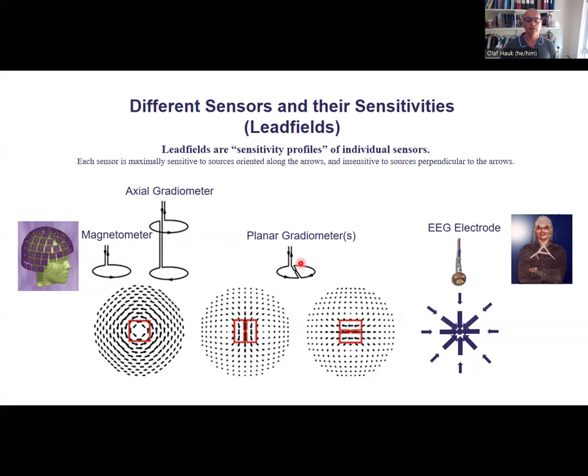And then there are also planar gradiometers. In this case, you have a similar arrangement. One coil here, one coil there. They are subtracted from each other, but they are next to each other in the same plane. It has the same effect. Homogeneous magnetic fields will cancel each other out. That means distant sources will be suppressed. Nearby sources will produce the biggest difference in these two coils. But this also has the effect that you have a different kind of sensitivity profile here, a different kind of lead field. And now the source that's underneath the sensor actually produces the biggest difference. That means in this case, if you put a lot of them around the head and you see a peak in your distribution without doing any source localization, you have at least some evidence that there is a source close by.